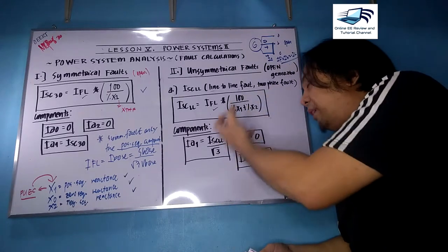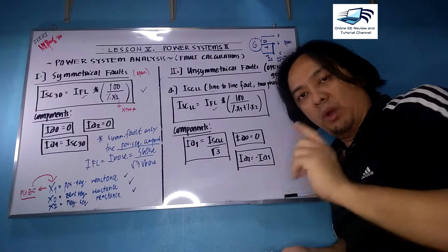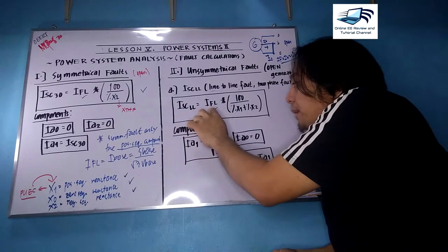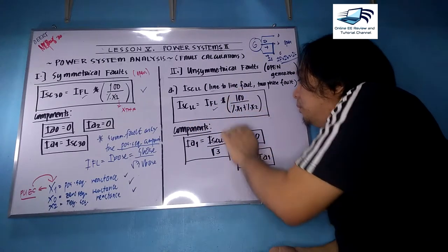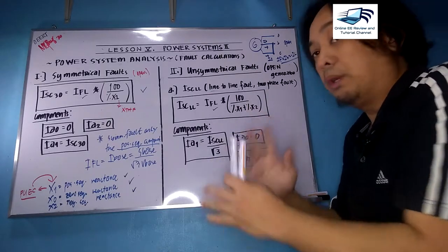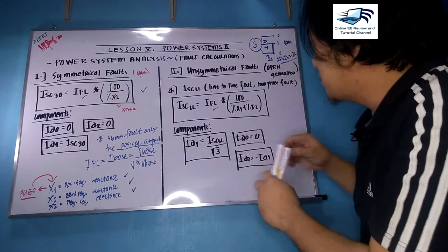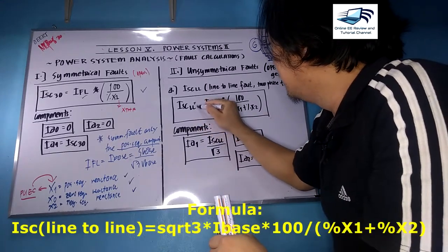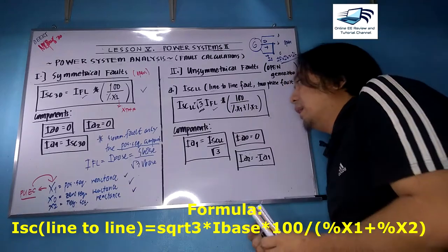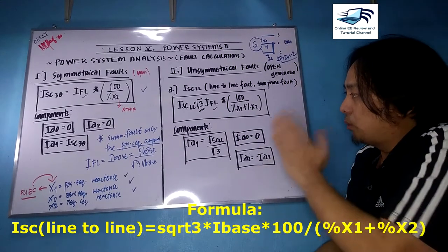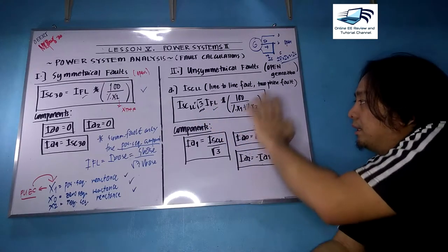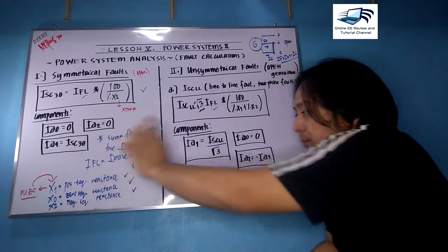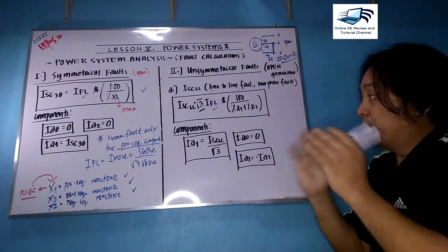Based on the derivation, ISC line-to-line is equal to the square root of 3 times the base current times 100, all over percentage X1 plus percentage X2. There is a square root of three in this formula. So ISC line-to-line equals square root of 3 times the full load current times 100 over percentage X1 plus percentage X2 — your positive and negative sequence components of the reactance.